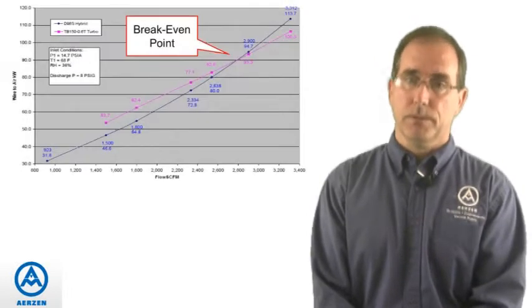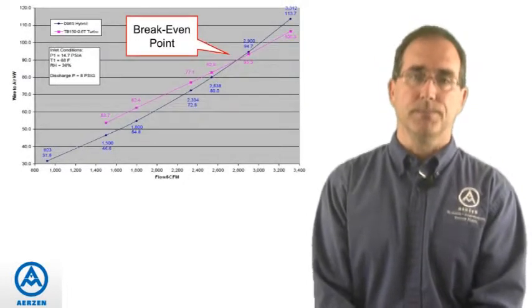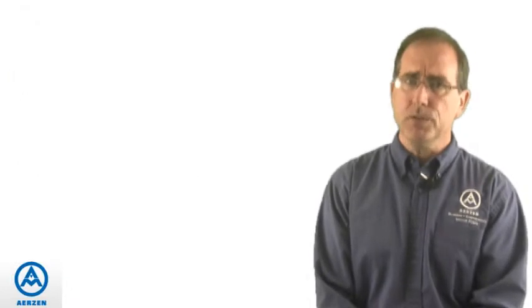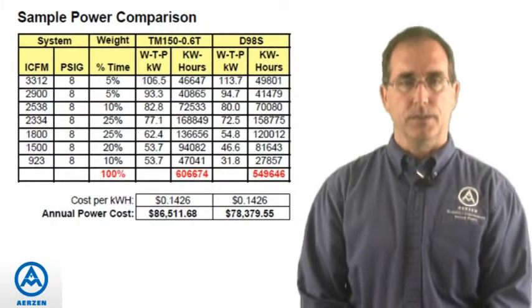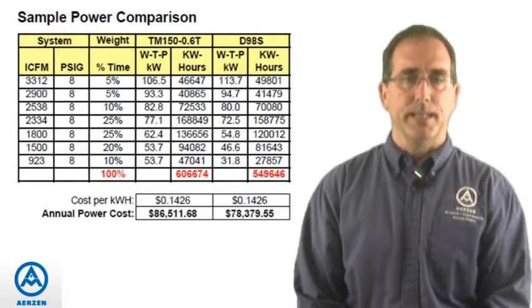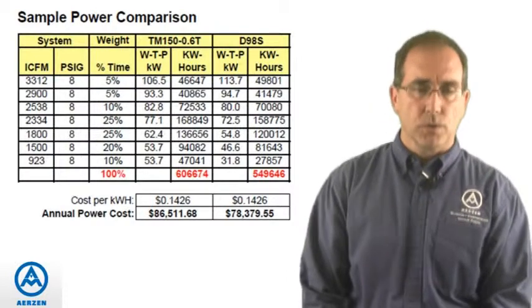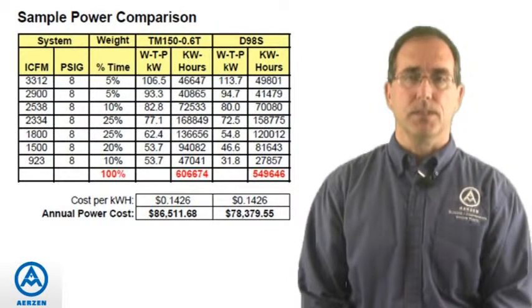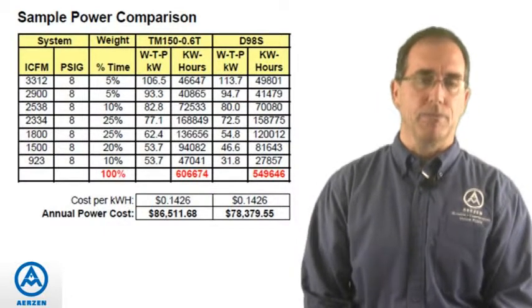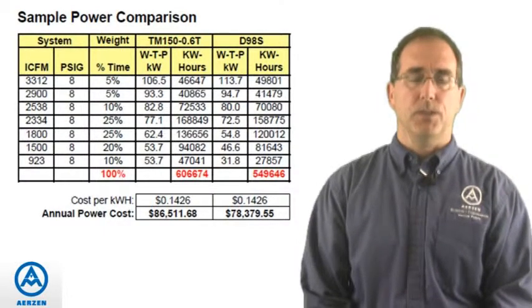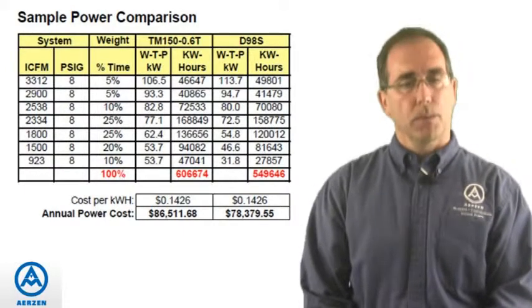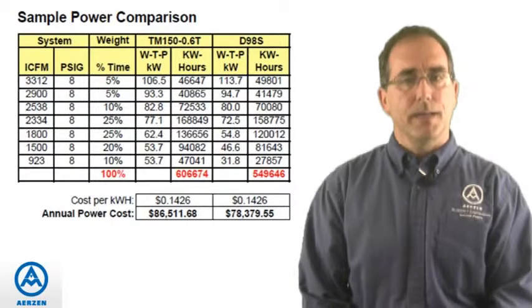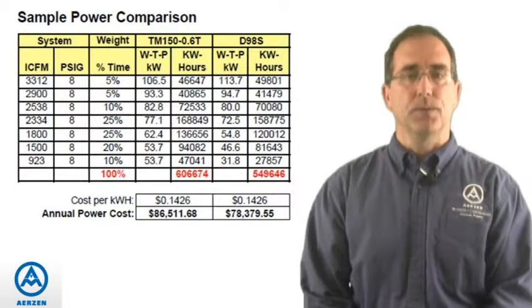Here's one more example where it's pretty much a toss-up between the two. You can see there's a break-even point between the turbo and the hybrid. So what do you do? You do what's called a sensitivity analysis — you take the curve, determine how often the system requires different flows within that range, assign a percentage of time, determine the total power required, annualize it, and add it up. That will help in your decision.